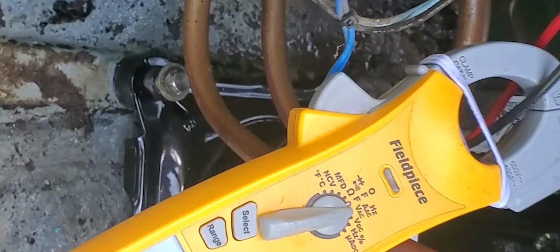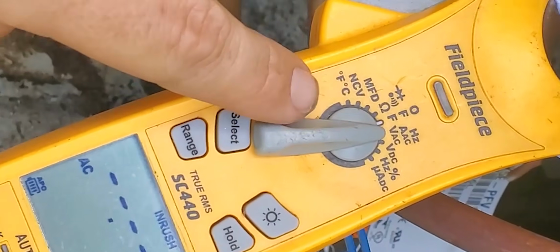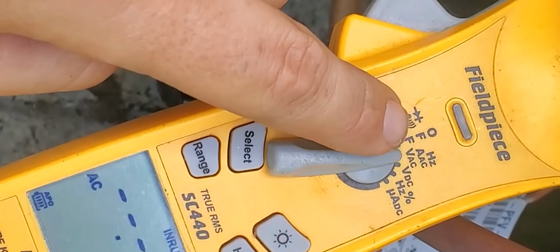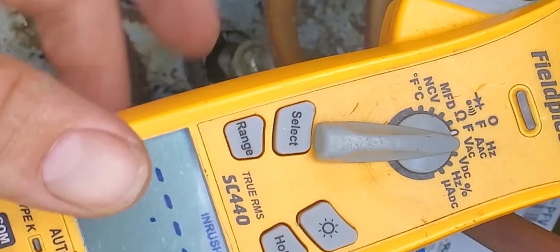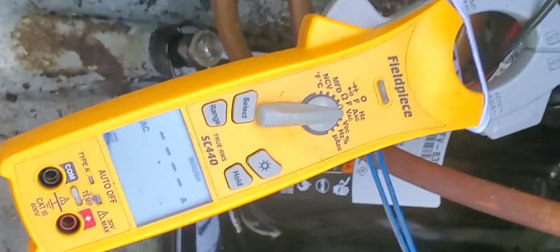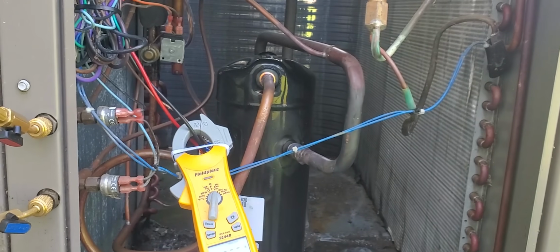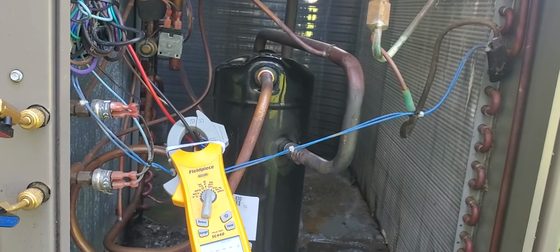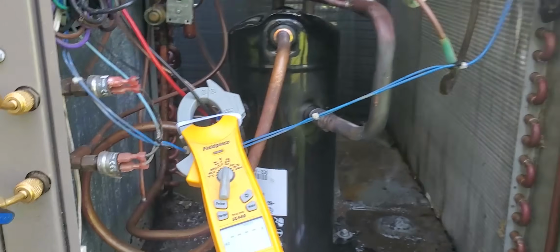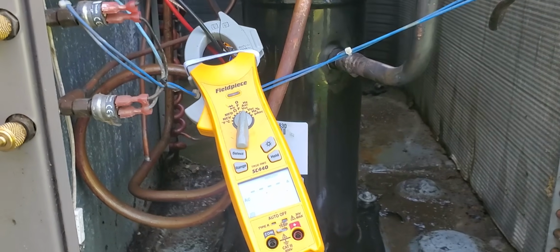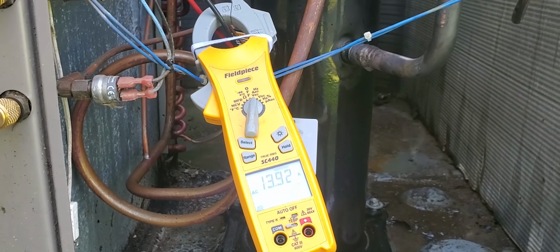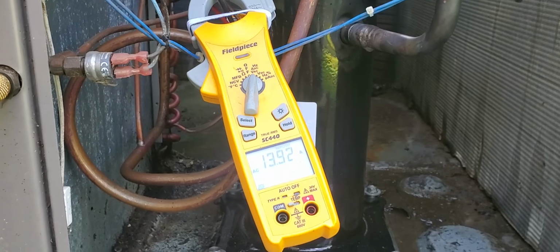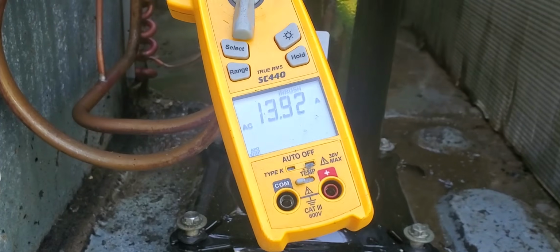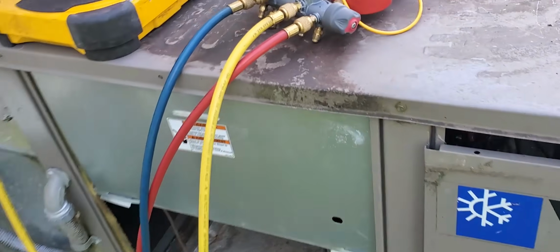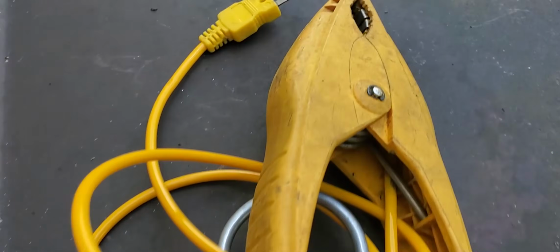How do we check inrush current? With the Fieldpiece meter, you put it in line with VAC, AAC. You push select, and then you push inrush right there, that button. Let's see what happens. New compressor, new indoor coil, new outdoor fan motor. This is practically a brand new unit now. Wow, 13 amps on startup, 13.92. Very nice.